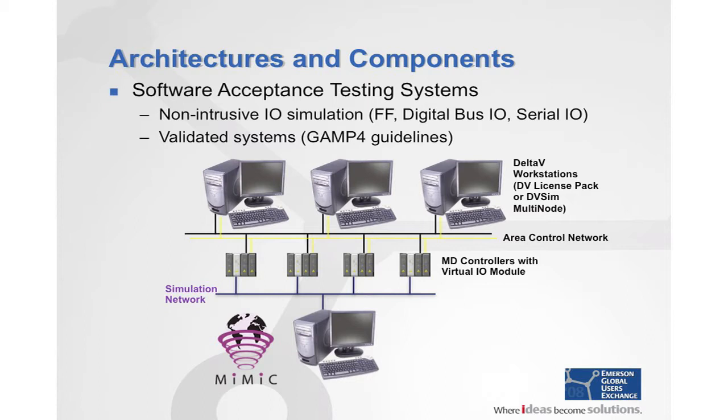Over a standard Ethernet network, the controllers talk back to the MIMIC machine. This gives us complete non-intrusive I/O simulation of your complete I/O subsystem. The process models reside in MIMIC and give you everything from simple PID and I/O models to very complex models, depending on what you want to do with them.